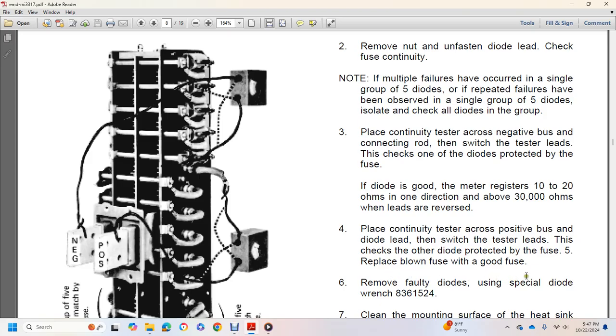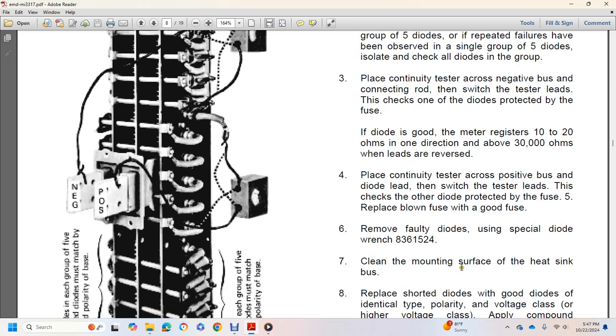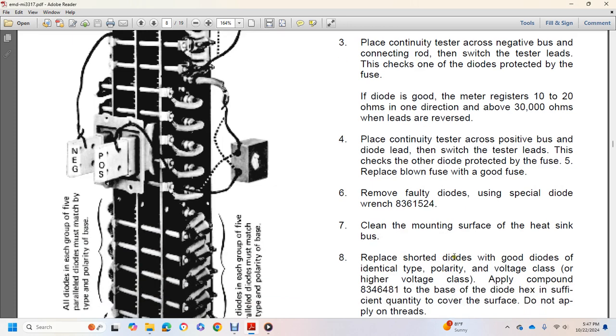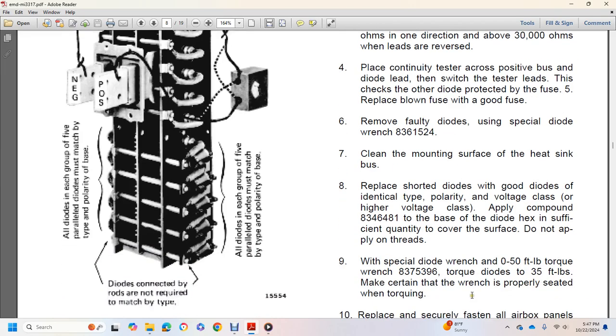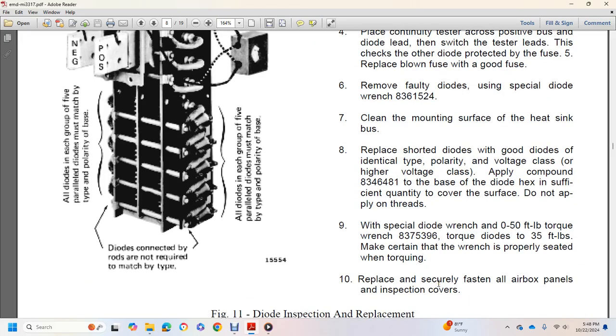6. Remove faulty diodes using the special diode wrench. 7. Clean the mounting surface of the heat sink bus. 8. Replace shorted diodes with good diodes of identical type and polarity. Apply voltage compound to the base of the diode hex in sufficient quantity to cover the surface; do not apply to the threads. 9. Using the special diode wrench and a 0 to 50 foot-pound torque wrench, torque diodes to 35 pounds. Make sure the wrench is properly seated when torquing. 10. Replace and securely fasten all airbox panels and inspection covers.